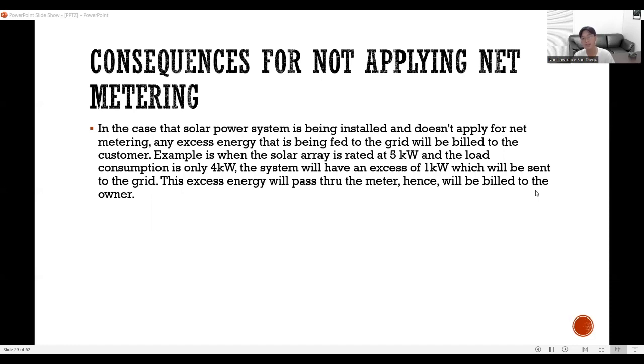So, what are the consequences for not applying net metering? In case the solar power system is being installed and doesn't apply for net metering, any excess energy that is being fed to the grid will be billed to the customer. Example is when the solar array is rated at 5 kilowatts and the load consumption is only 4 kilowatts, the system will have an excess of 1 kilowatt, which will be sent to the grid. This excess energy will pass through the meter, hence will be billed to the owner.